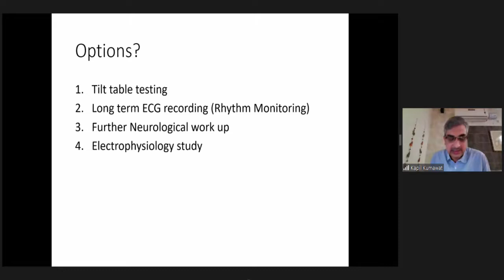So we decided to do a long-term ECG recording. We did a long-term Holter and not long-term ELR. This is an in-house developed Holter system designed in collaboration with a startup cardio design lab. It uses a single AAA battery in the recording system, which is attached to the 4 leads. And this can be communicated to a handheld mobile given to the patient, which can continuously transmit data to the call center, especially the alerts.